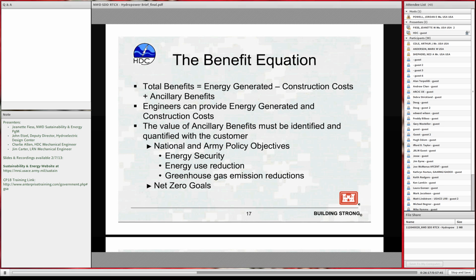This is what I call the benefit equation. When you get right down to it, this is the crux of the decision process for whether or not you're going to actually build a new hydro-generating facility. The total benefits of a generating unit over its lifetime is basically equal to the energy that's generated over that lifetime, minus the construction costs to build it, minus the operating and maintenance costs to run it over its lifetime, and then plus the ancillary benefits. We on the engineering side of the house can do a real good job of providing values for energy generated over its lifetime, the O&M costs, and the construction costs.